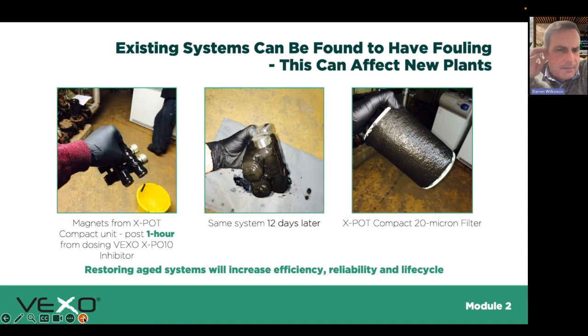I remember anecdotally, the people who worked in that building - it used to be a cinema, then a retail store - always had trouble in a hard winter getting the place up to temperature. It later transpired the boilers were undersized too. But by cleaning up that system, the air handling coil on-off temperatures were much better, and staff said it was the first time they hadn't been cold in the winter. The impact on overall system efficiency can be huge.